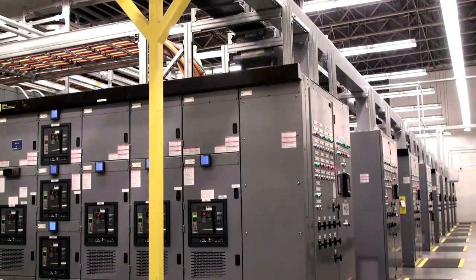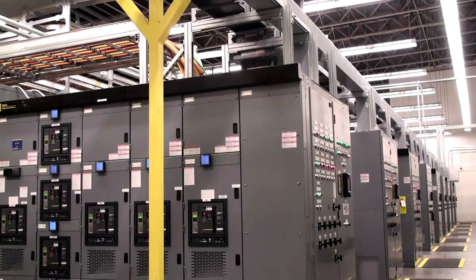The second patent that we have is a distributed redundancy system, and it's on the secondary of our transformers for the customer load. What it allows us to do is move live load between UPSs. It also allows us to expand and get maximum efficiency from our UPSs. We've had cases where a breaker will trip on a customer's redundant circuit, and we can actually move that entire load to another UPS, replace the breaker, move it back without any outages whatsoever. So that's something that is intellectual property that nobody else has.